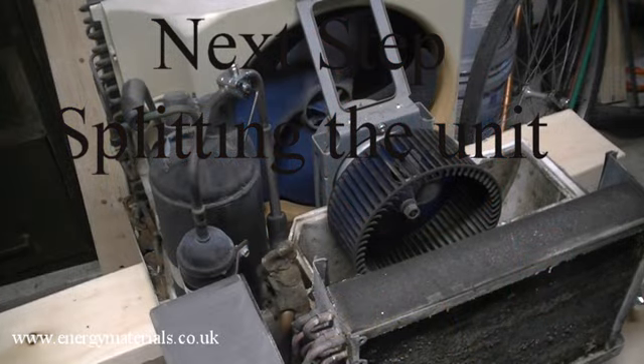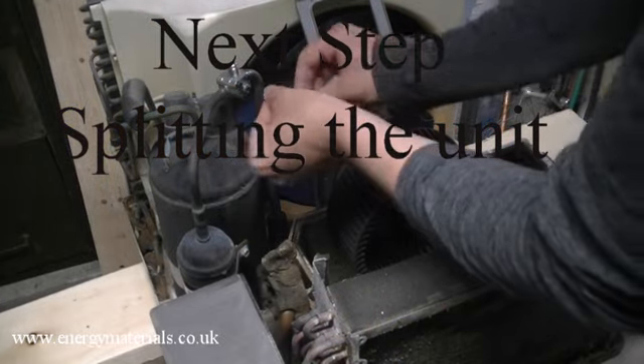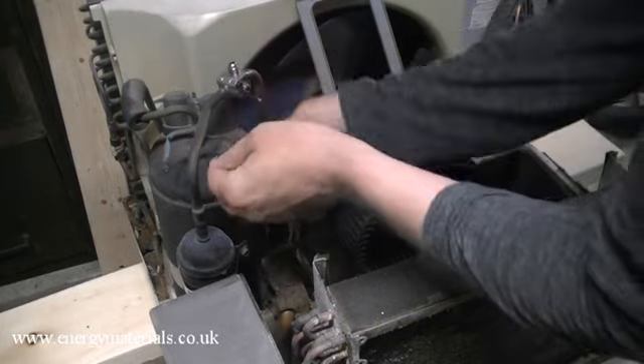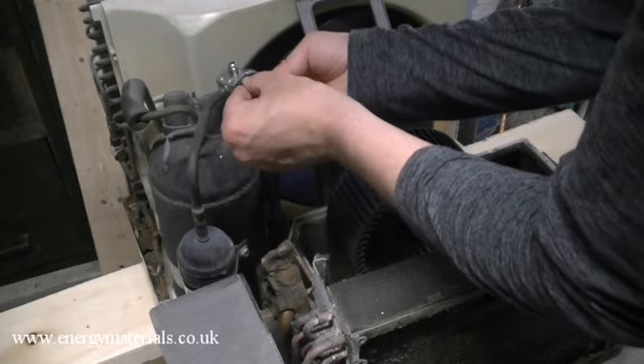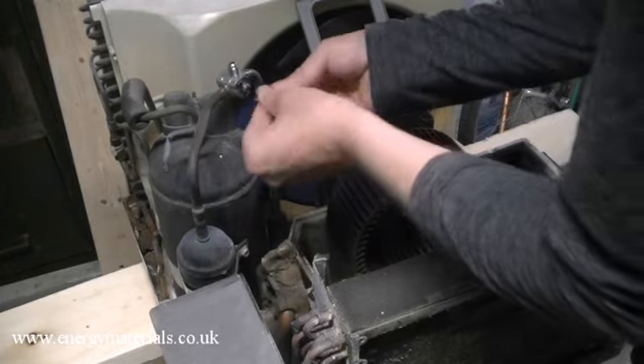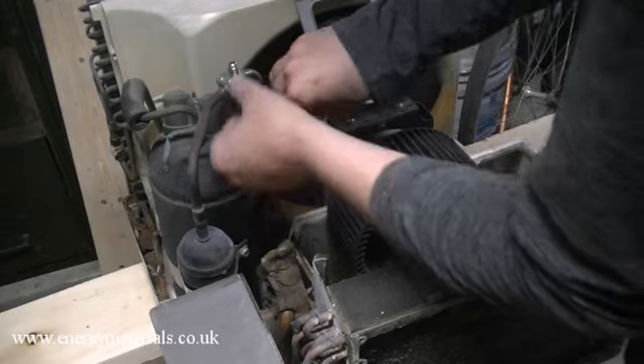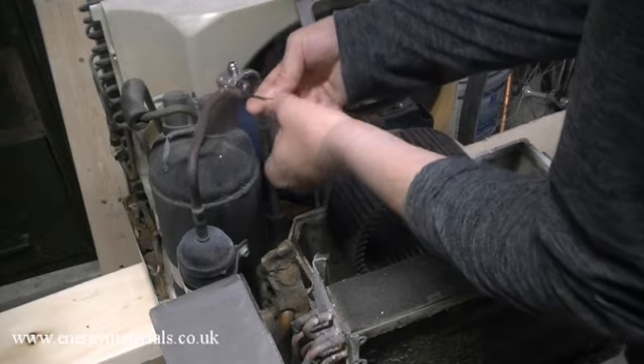Okay, so the refrigerant is out of the system. Let's take this clamp off and see if we can split the unit to get our evaporator and our condenser separate. So this did the job.